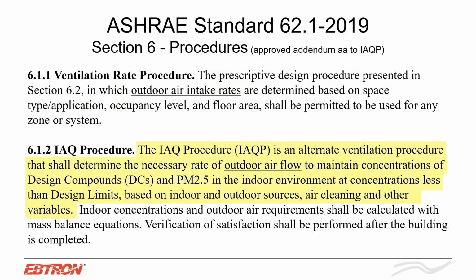You also have the IAQ procedure, an alternate ventilation procedure that basically determines the necessary outdoor air to maintain certain concentrations of contaminants under a certain level. Right, so you have to do the math and figure out what the airflow rates are depending on the contaminants in the space. Doesn't matter what you design to, both of these are rate-based standards. And what does that mean? Again, if they're rate-based standards, you have to be measuring and controlling to comply with the standard.